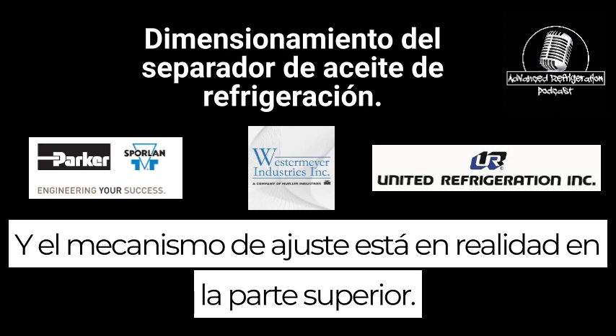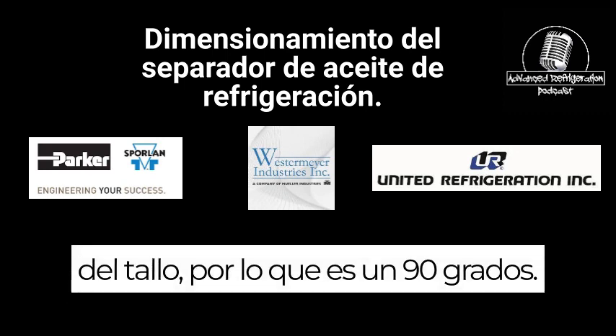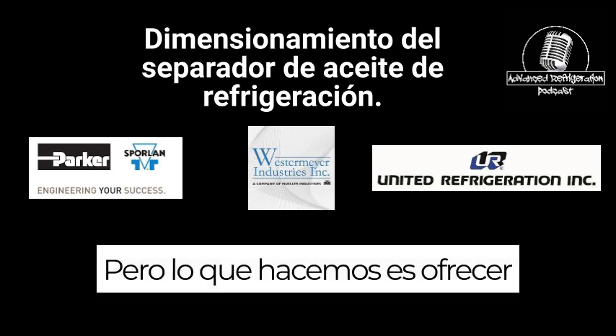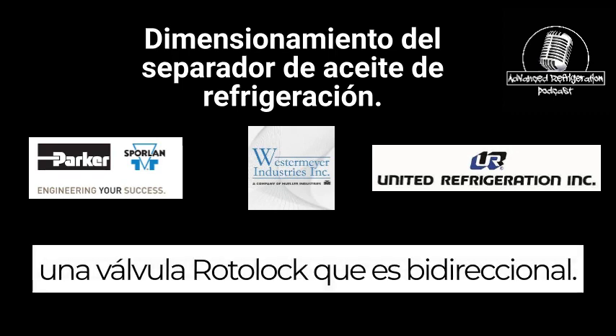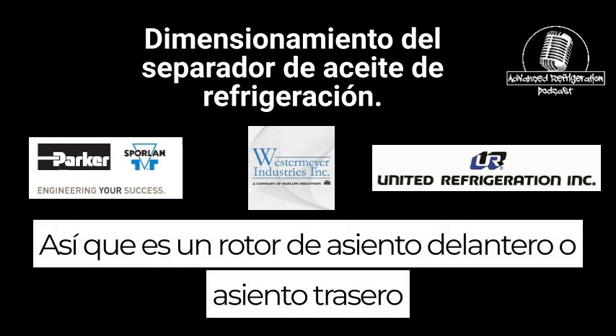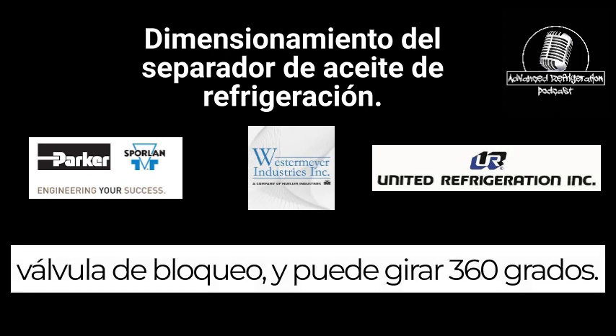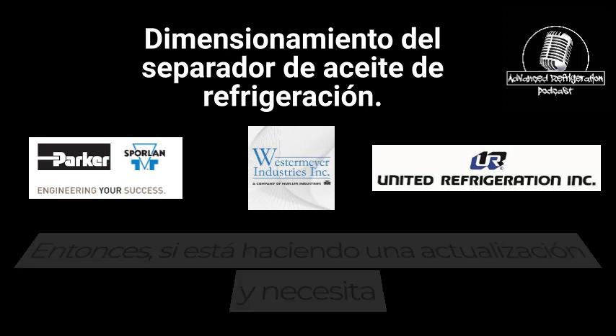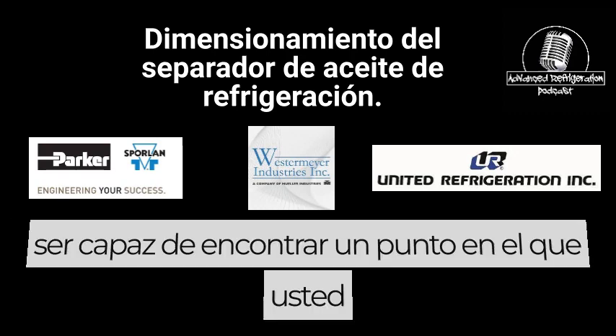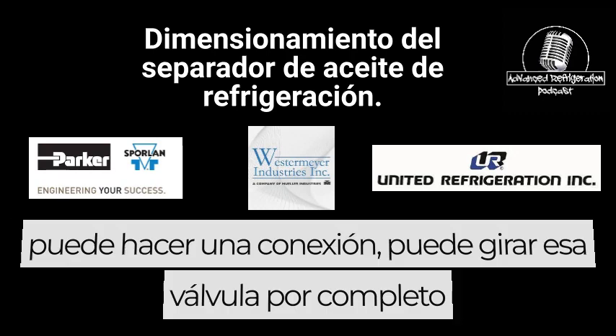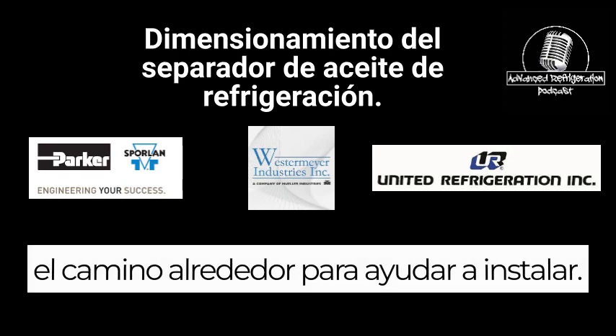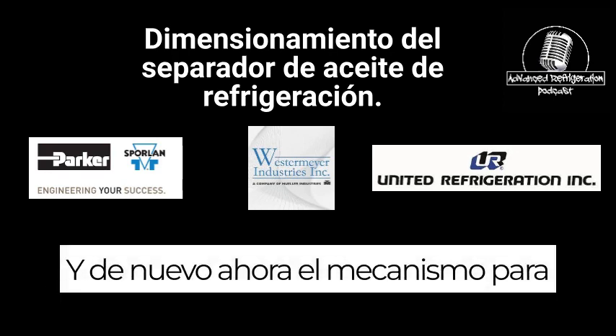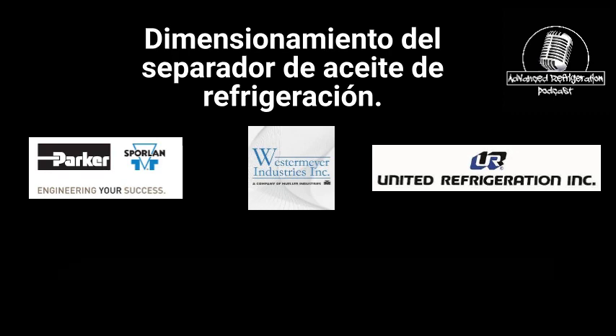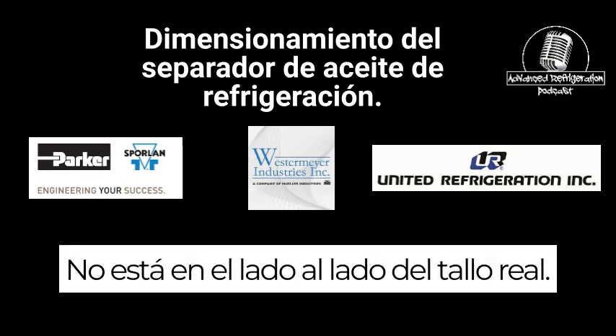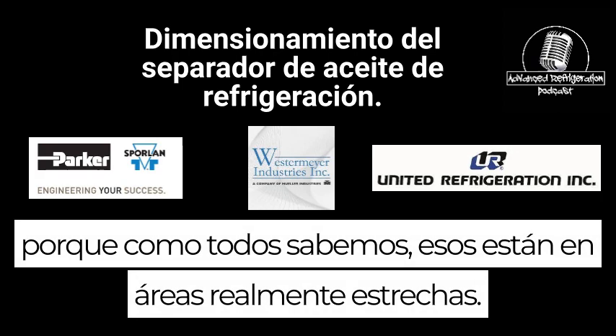The adjustment mechanism is actually on the top of the stem, so it's a 90-degree. We offer a rotolock valve that's bidirectional, so it's a front-seating or back-seating rotolock valve, and you can swivel it 360 degrees. If you're doing a retrofit and you need to find a point where you can make a connection, you can swivel that valve all the way around to help with install. Again, the mechanism for adjustment is all on top, not on the side next to the stem itself, because as we all know, those are in really tight areas.